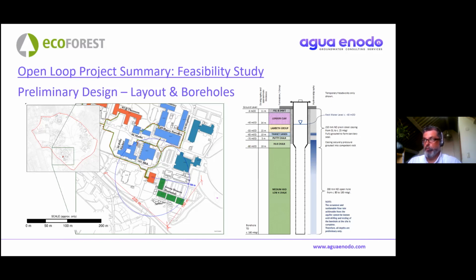We also need to know the pump depth, because when we switch a pump on in an abstraction borehole, we draw the water level down, and we have to predict the level to which that water will fall. Based on that we can start specifying pumps, bore diameters, and bore depths. That's a fairly typical preliminary design of an open loop borehole.